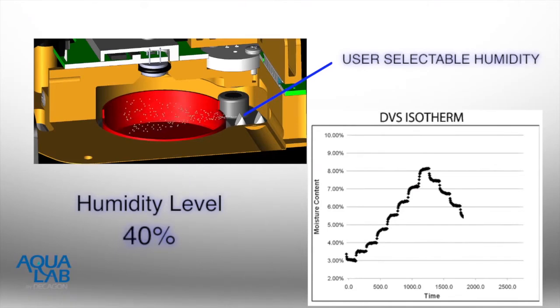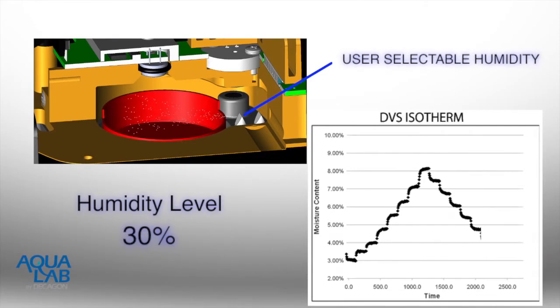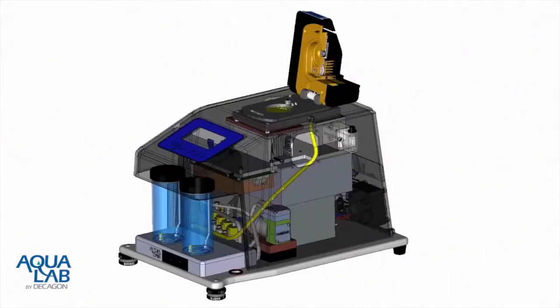The Aqualab VSA can produce DVS isotherms that are equivalent to those produced by any existing vapor sorption analyzer, but it can also use the DDI method. The DDI method is a truly dynamic method and produces dynamic isotherms.